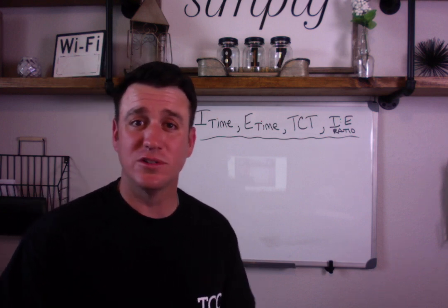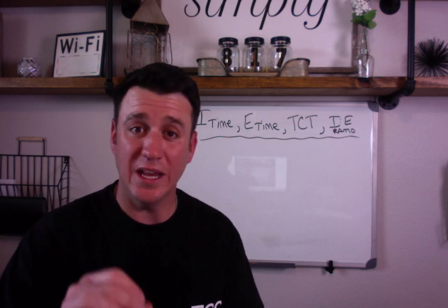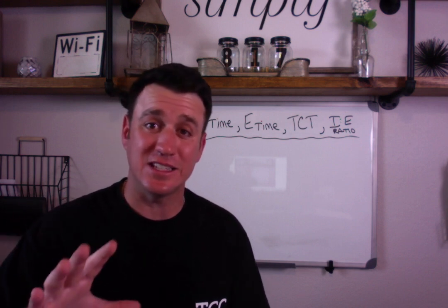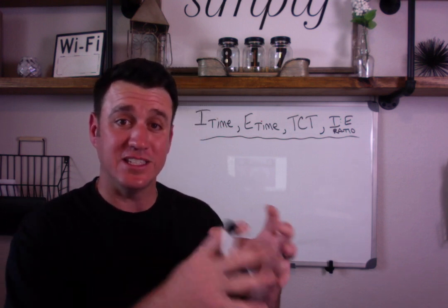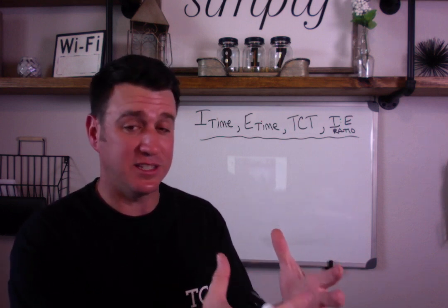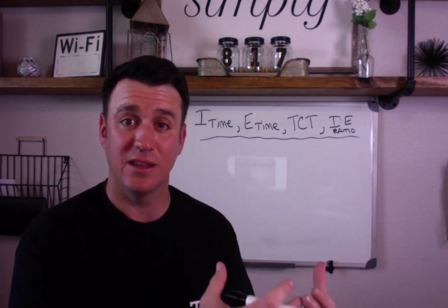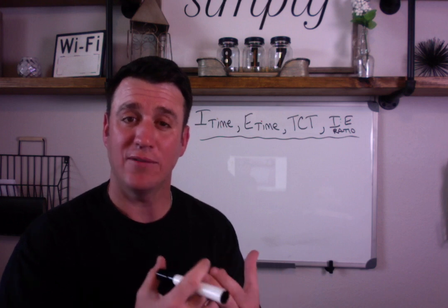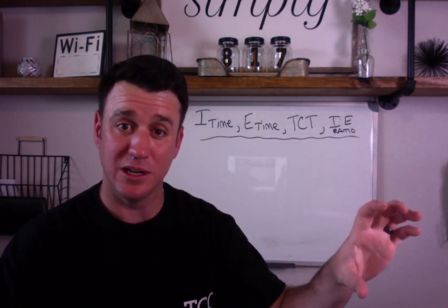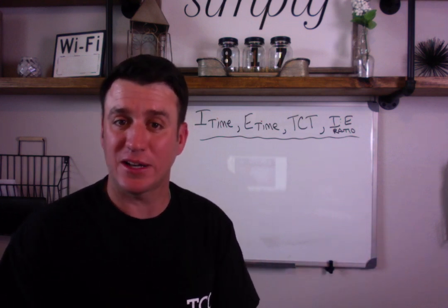Okay, so everybody knows that our formula for calculating I time, when you're in volume control, this is talking about delivering a set tidal volume. If you're going to deliver a set volume, the amount of time it takes to deliver that set volume depends on how fast you're delivering that set volume, okay? So you have to understand that first of all. What's my tidal volume? Because that's the amount that's going to be delivered. And then how fast am I giving it? So that brings us back to flow, okay?